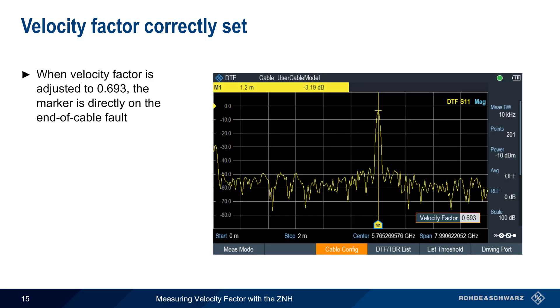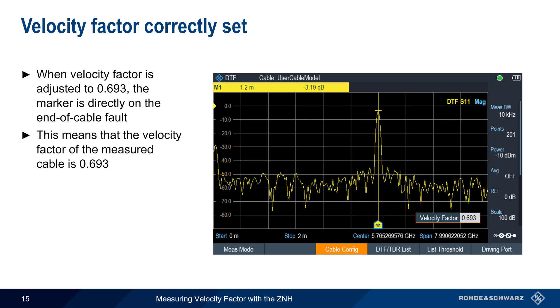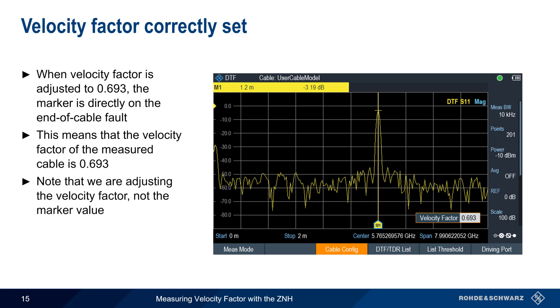After a little more manual adjustment, we find that setting velocity factor to 0.693 causes the marker to fall directly on top of the end-of-cable fault, and this means that the velocity factor of the measured cable is 0.693. It's important to keep in mind that throughout this process, we've been adjusting the velocity factor. The marker remains stationary at the manually configured length value of 1.2 meters for this specific cable under test.